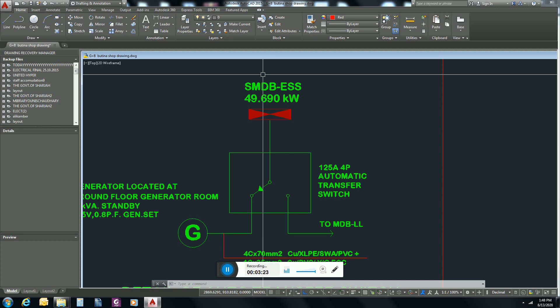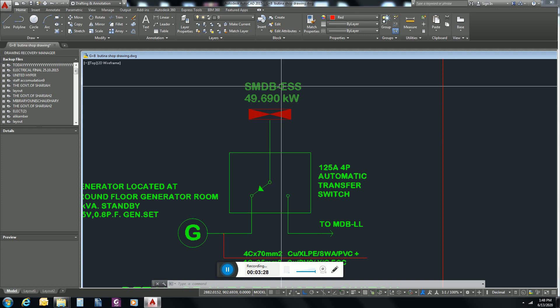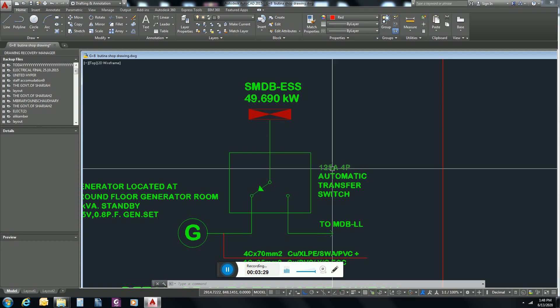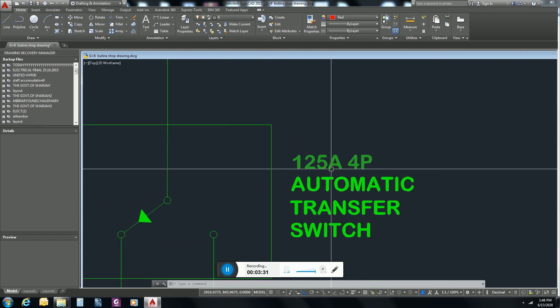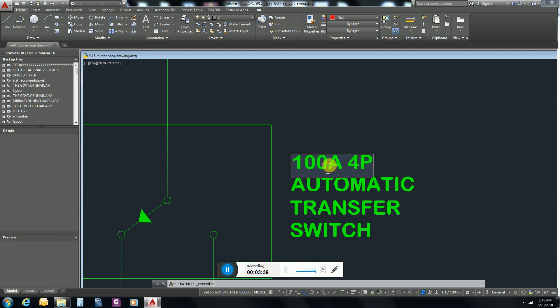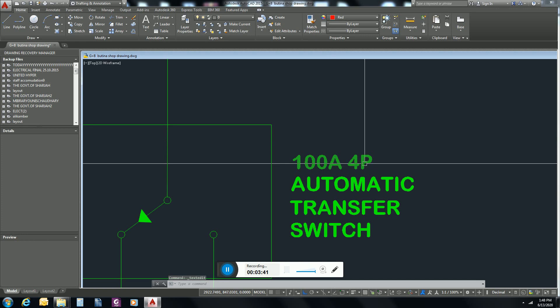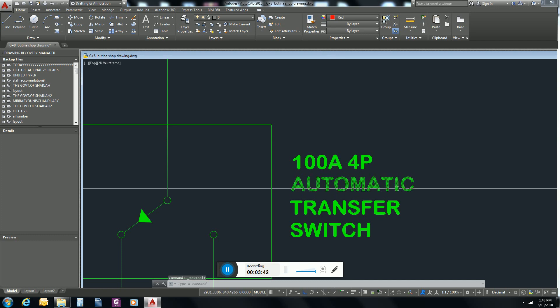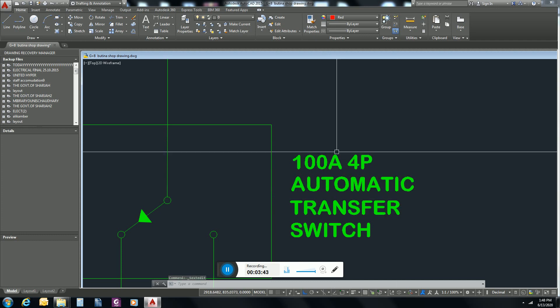After converting this kW power to ampere, its ampere rating will be 86, but we don't have any MCCB of 86 ampere. That's why we will write here 100 ampere 4-pole automatic transfer switch.